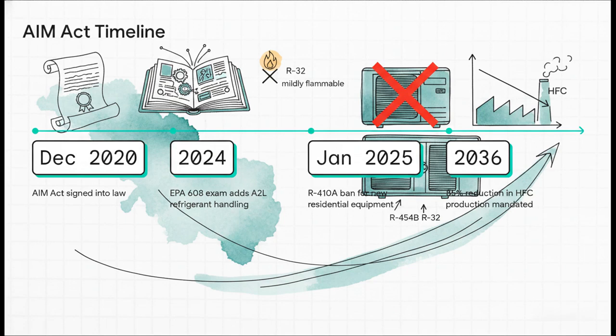The AIM Act, signed back in December 2020, mandated an 85% reduction in HFCs by 2036. But here's the immediate operational impact: as of January 2025, there's a strict ban on R410A for new equipment. To adapt, the whole industry is shifting to mildly flammable A2L refrigerants like R454B and R32.